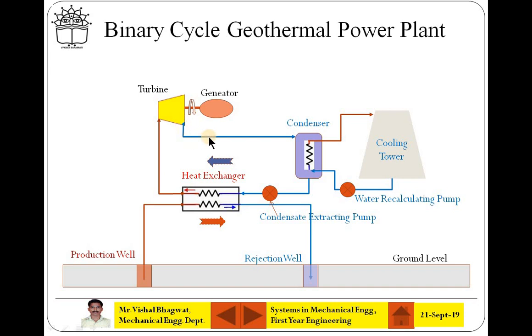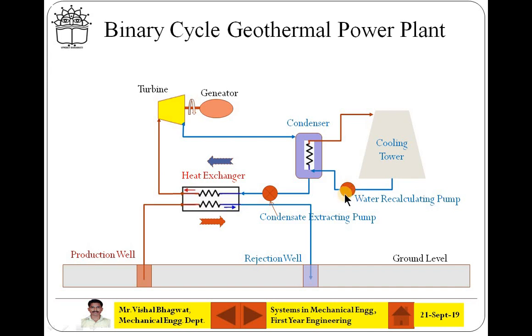Now, this low pressure steam is collected to the condenser. In the condenser, this steam is condensed and converted into liquid. Again, that low pressure organic liquid is pumped back to the heat exchanger with the help of condensate extraction pump. In the condenser, what is happening? The cool water from the base of the cooling tower is circulated with the help of recirculating pump and it is going inside the condenser coil.